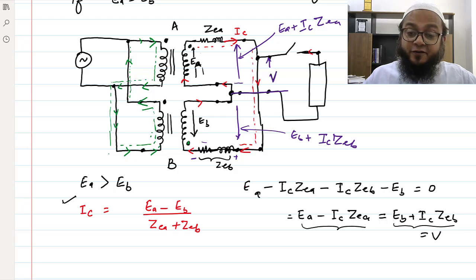Even if you have not connected any load, because of the difference in induced EMF—caused by a difference in the voltage ratio—there is a difference in induced EMF at the secondary of both transformers. Once you short the secondary, it forces a circulating current in the secondary, and because of that there is a circulating current in the primary as well. Obviously the transformer will have more losses even at no load, because of the change in induced EMF in the secondary side; there would be a circulating current causing more losses. So this is not an efficient way.